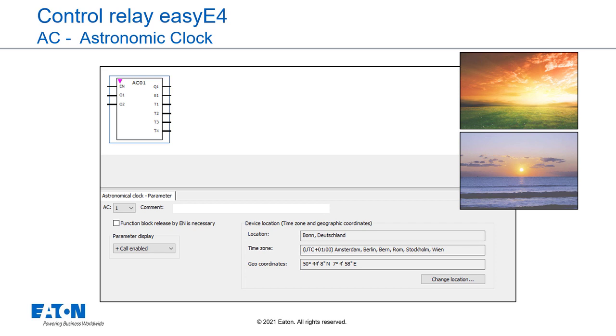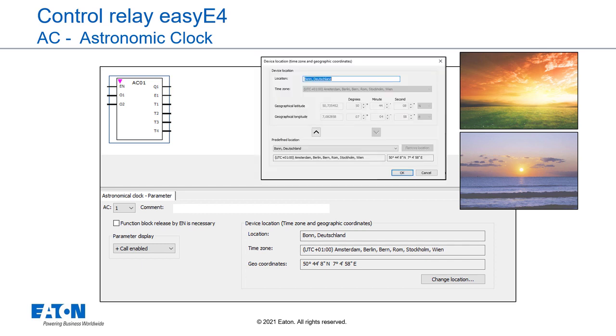Output Q1 is switched for the time between sunrise and sunset. The device location is defined in the project view at the clock tab. The device time can be checked and changed directly at the device or in the view communication in the section clock.